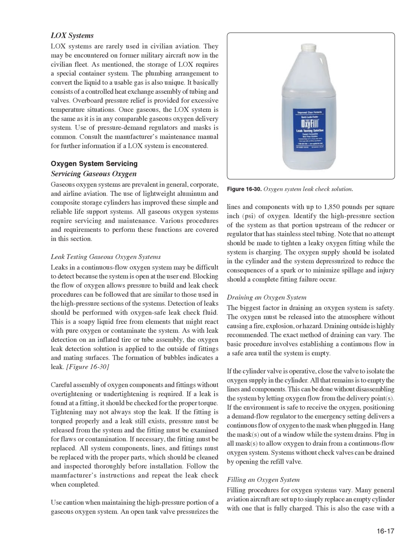If the cylinder valve is operative, close the valve to isolate the oxygen supply in the cylinder. All that remains is to empty the lines and components. This can be done without disassembling the system by letting oxygen flow from the delivery points. If the environment is safe to receive the oxygen, positioning a demand flow regulator to the emergency setting delivers a continuous flow of oxygen to the mask when plugged in.